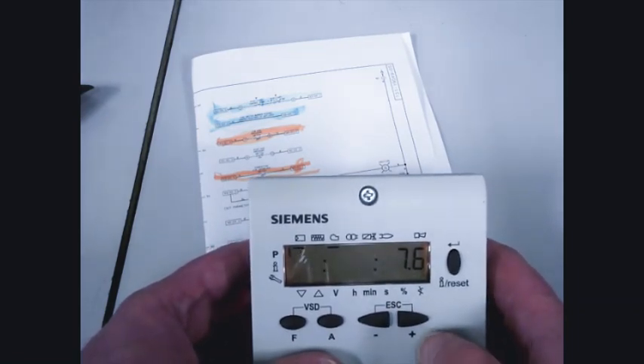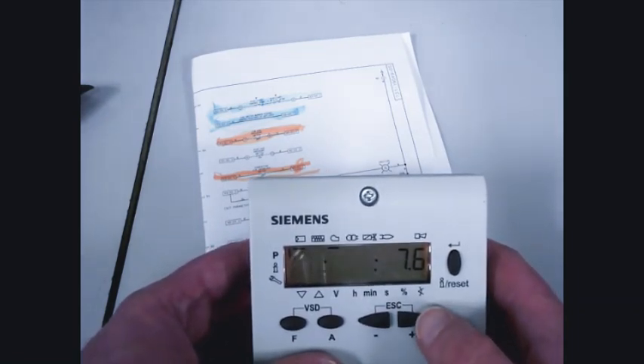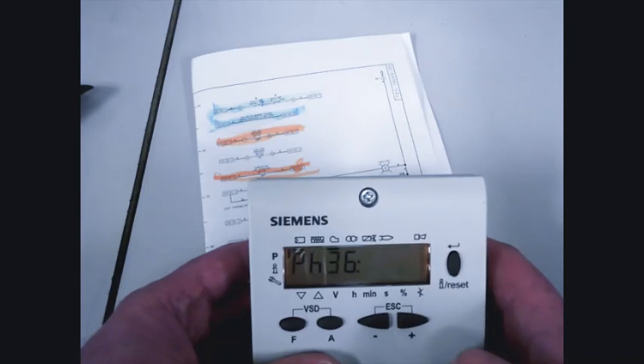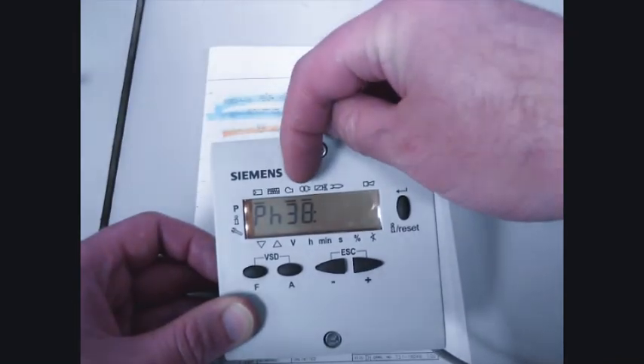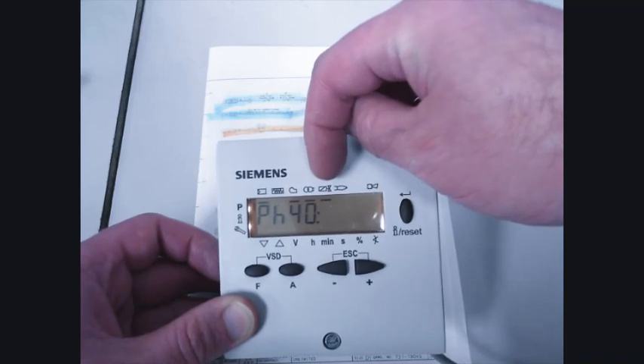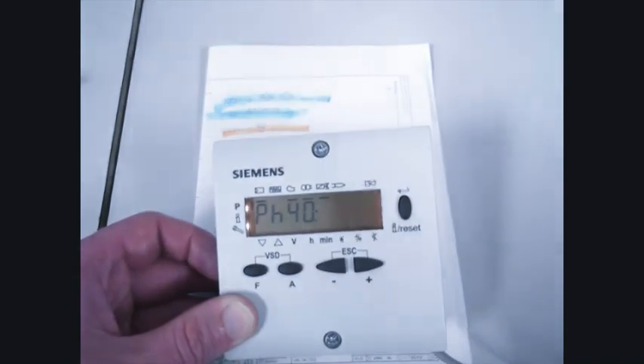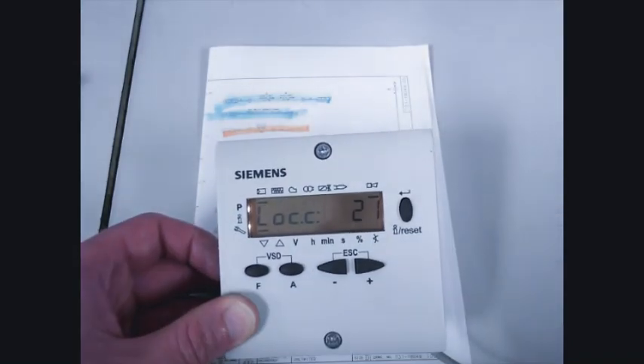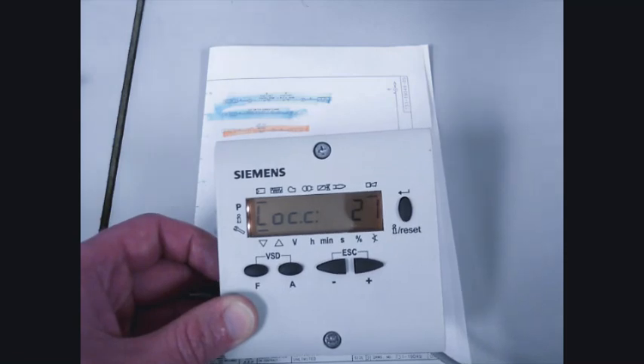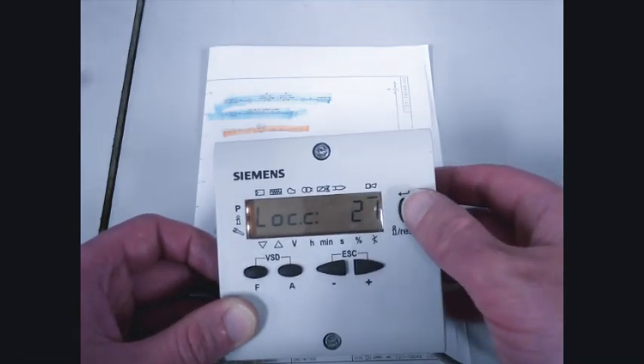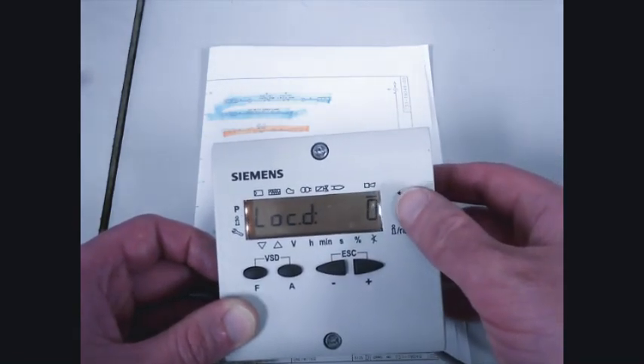When we are satisfied with our light off position, we press plus. We see the ignition transformer icon and main fuel activate, but we get an error message. Turn the burner switch off — lockout code 21, diagnostic zero.